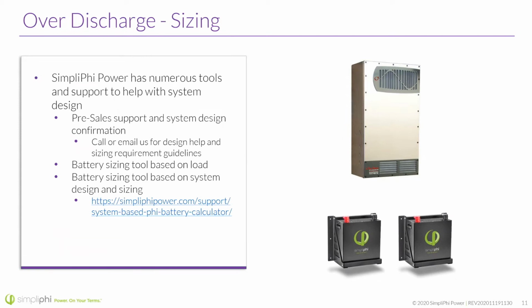SimpliPhi Power has numerous tools and support to help with system design. If you're having any issues or you're concerned about over discharge with sizing, we offer pre-sale support and system design confirmation. We have sales application engineers on the line ready to talk through sizing. So it's never a bad idea if you're just a little curious, maybe not 100% sure that your sizing was correct on a few of these systems. Maybe systems you already put in place, just give us a call. We can work through it and make sure we get everything correct before we see damage. The battery sizing tool based on system design and sizing is the real one you want to use. There's the link for it, and you'll have that after this presentation goes out. That's the real link you want to use for sizing based on system design to avoid over discharge.